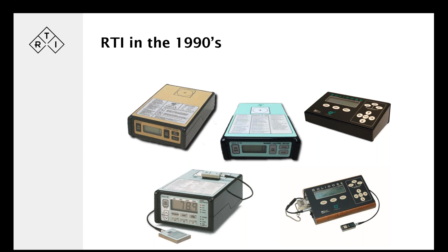So we move a little bit forward. 30 years ago, this is what the hottest equipment looked like then. It's the PMX range that we see here, which is quite popular. And I'm sure that some of you have worked with them. And if not, you probably would have seen them somewhere in the storage, on the shelf, because there were quite a few that were out in the field and still are in the field. We still get them back for calibration. Solidose is dedicated for dose only. PMX here has both dose and kV. But Solidose is a range that also comes back in for calibration, although they're 30 years old. So they're quite solid.